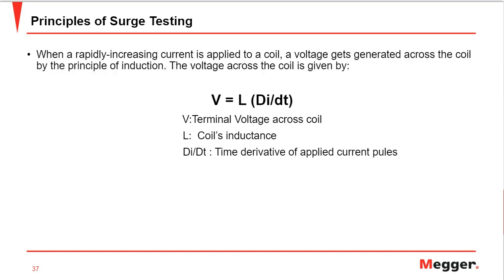So ultimately, what the surge test does is create an induced voltage between adjacent coils or adjacent turns, and it detects the arcing, which is indicative of a weak or failing insulation. Surge testing tries to replicate the real life scenario while doing the test.